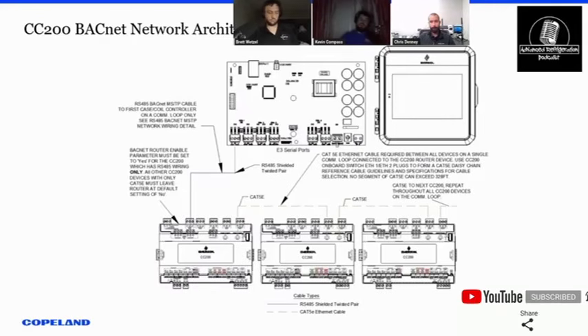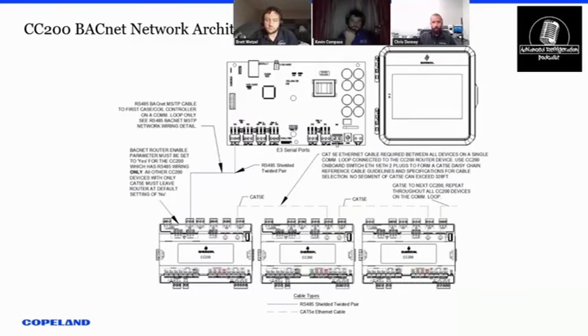Now, does the E3 have a dedicated Ethernet port in there that's not on the customer side, or is that something that has to be on the customer's network too? We can do it both ways, but the easiest, probably pain-free way without dealing with IT and going through all that is to use that spare Ethernet port on the E3. So the E3 has 3 Ethernet ports on the back of the door, one for the PIB board and display, one for the customer WAN network, and then one available one, which is where you can hook your laptop or where you can hook BACnet IP devices. So we'll use that third one to hook up the case controller network.